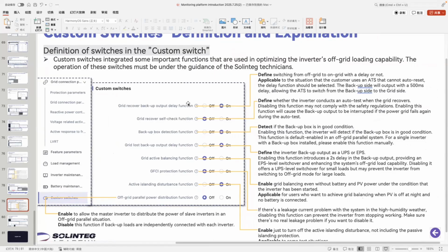This function is mainly applied in situations where some customers didn't connect the backup load to the backup port on our inverter. Instead, they use an ATS to control all the backup load and connect the ATS to the inverter, and some of these ATS are maybe older versions. When the grid is cut off or doesn't work, the situation is very simple: the ATS will just choose another energy provider, that is, it will use the power from the backup side.